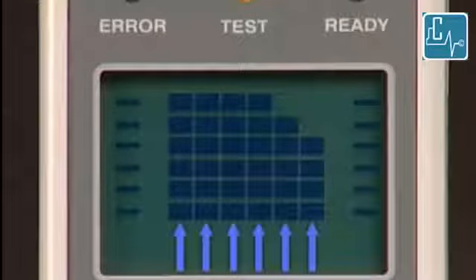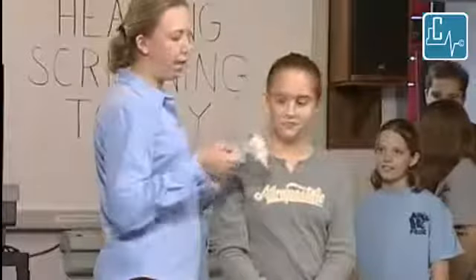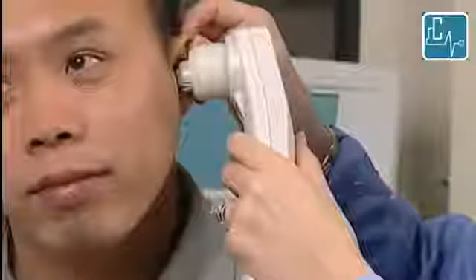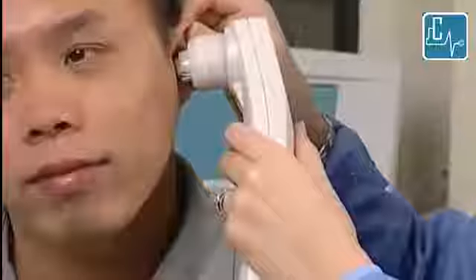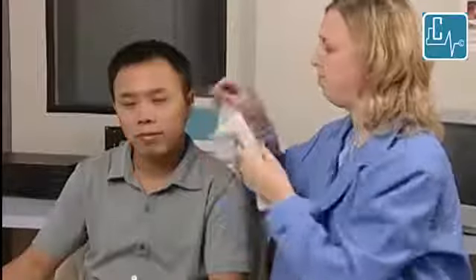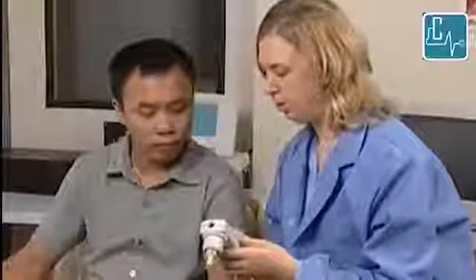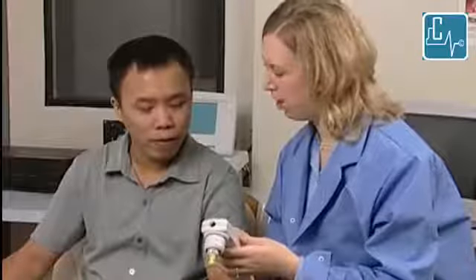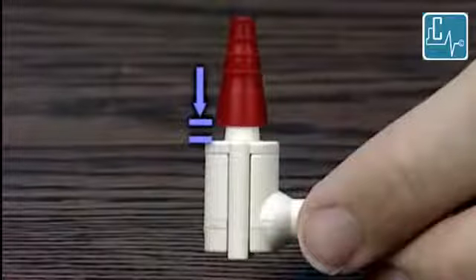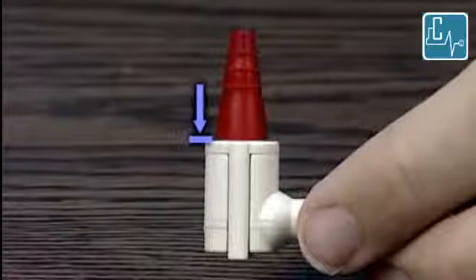The bars represent the signal-to-noise ratio of the emission at each frequency tested. Testing with the internal probe is similar to that of the external probe. Testing of children and adults uses the same basic principles. Select an ear tip appropriate for the patient. Keep in mind that the deeper the seal, the larger the emission. Therefore, selection of a smaller ear tip is generally preferable. Please note when using either the internal or external probe, make sure that the ear tip is fully seated on the probe.